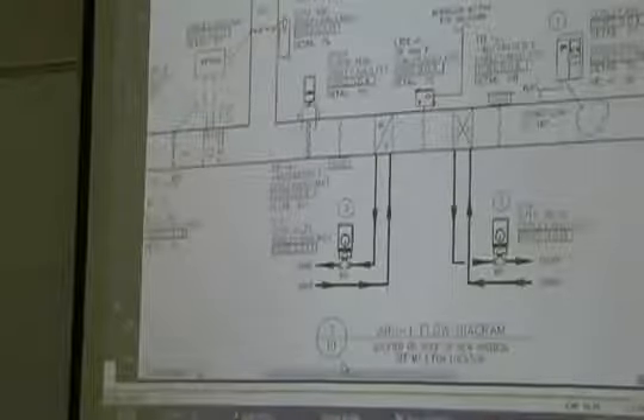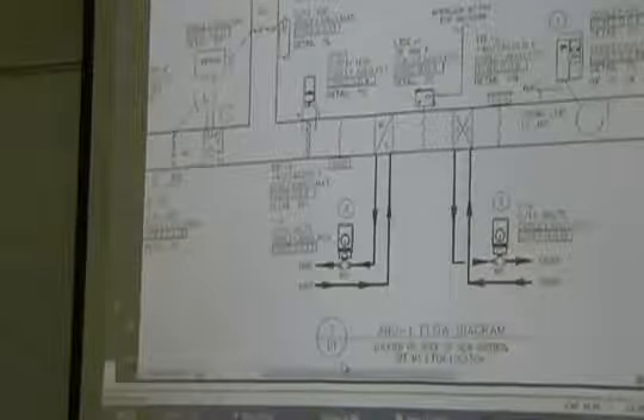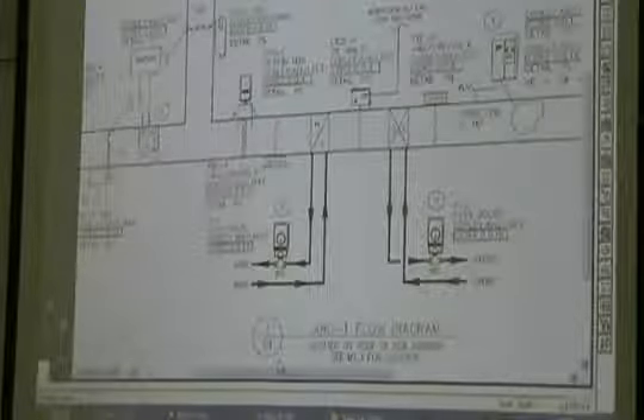Now, scooting back on the air handler, chill water coil, some kind of valve to control the flow of the chill water. And I don't know if we mentioned this last time, but where did we mount that chill water valve? On the return. Why do we do that? Darn, I was hoping somebody would tell me. It's always on the return, and the story I've always been told is that it keeps the pressure up in the coil. It doesn't starve the coil.